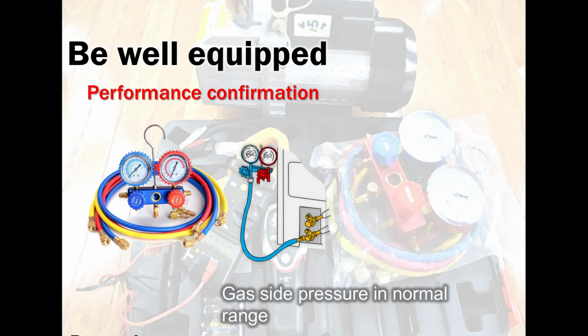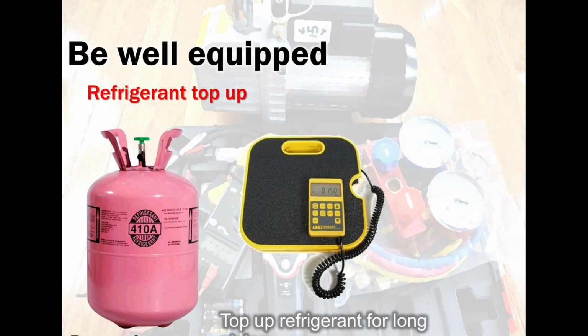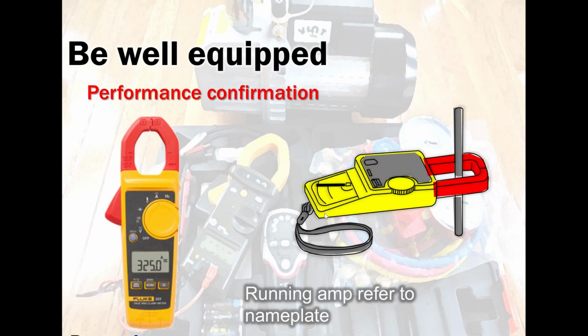When you have a problem, I always tell guys, use your amp meter first. Always use your amp meter first before hooking up your gauges. I don't like hooking up gauges, guys. I like using my amp meter first. Then if I need to use my gauges, I will tell them, okay, hook up your gauges. But check your running amps. Your running amps can tell you a lot of things.